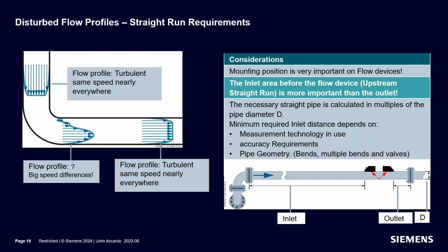So also, another thing that we see in the field is disturbed flow profiles. And disturbed flow profiles are due to limited straight run of pipe. When there's limited straight run of pipe because there's an elbow or a multiple elbow or an expander or a reducer or some other pipe geometry, it affects the way the fluid travels down the pipe. There's an old rule of thumb that says, well, when you install a flowmeter, you should have 10 diameters of straight pipe upstream and 5 downstream.